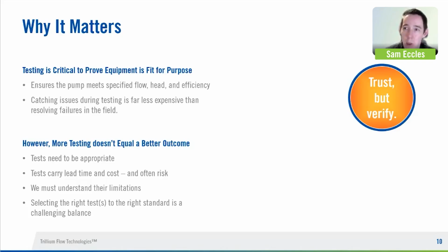Catching and rectifying issues at any stage is expensive. Doing it in the pump OEM's manufacturing facility is 1/10 of the cost of rectifying these issues at site. And above all else, we need to prove that the pump is a known quantity, so that when it goes into the system that has elevation changes that aren't quite to plan, it has a different pipework routing because something changed during the construction process.